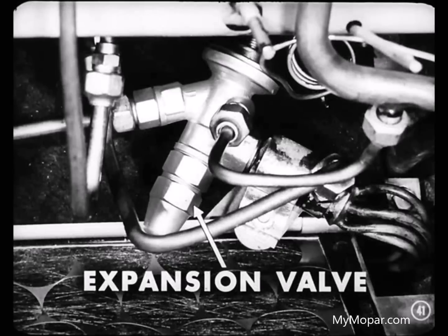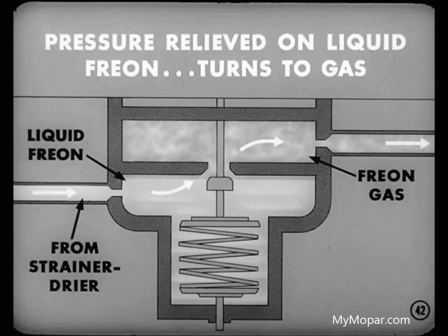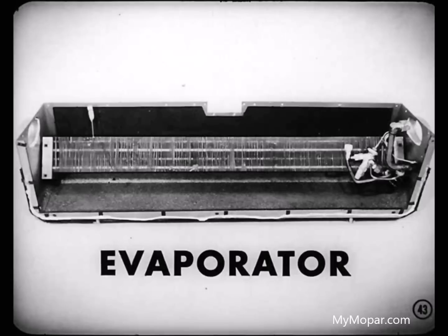Next, the Freon goes to an expansion valve, also located in the evaporator unit in the luggage compartment. You might compare this expansion valve with a valve on the steam heating system which feeds water into the boiler as needed. Actually, this expansion valve is a chamber in which the pressure on the liquid Freon is relieved so that it can start to change to a gas. So its temperature starts to drop as the pressure drops.